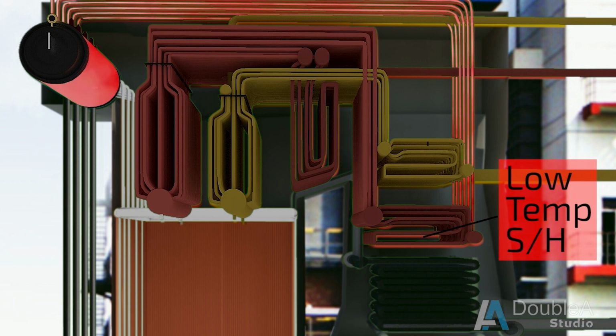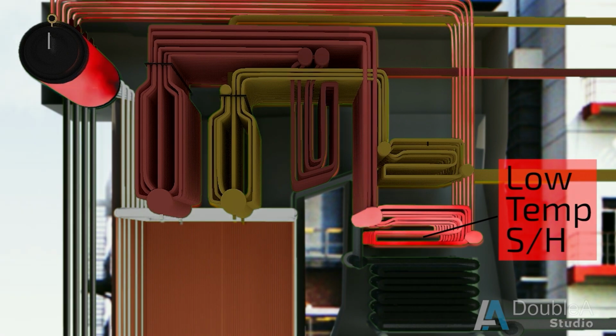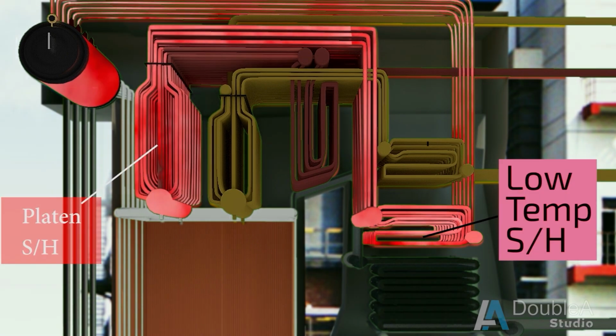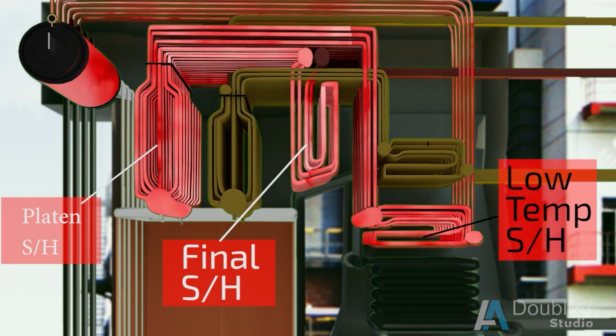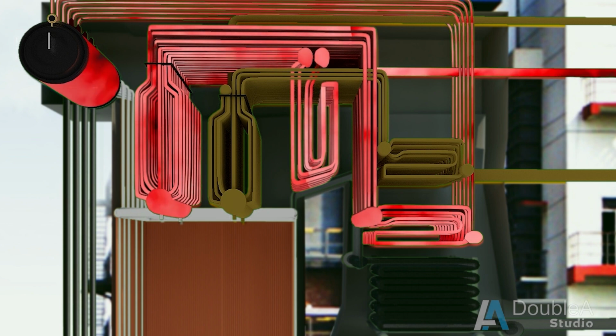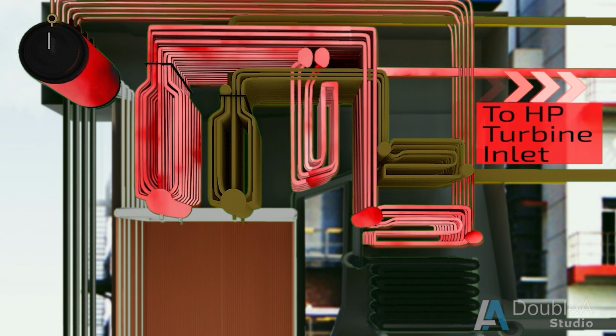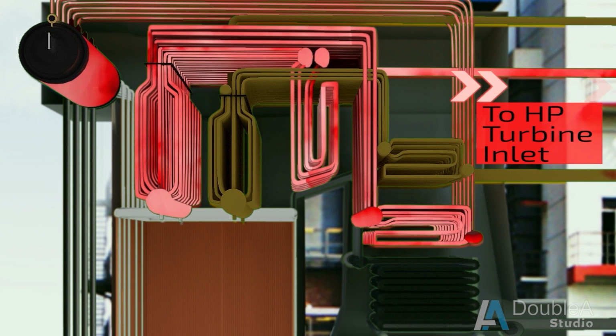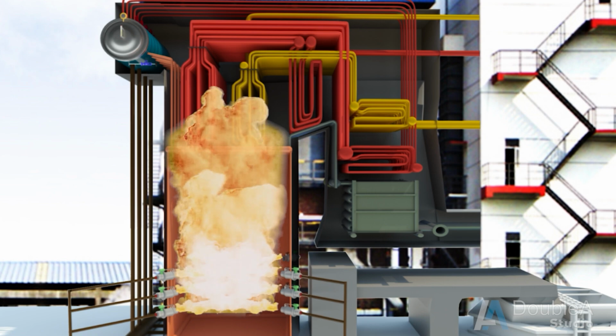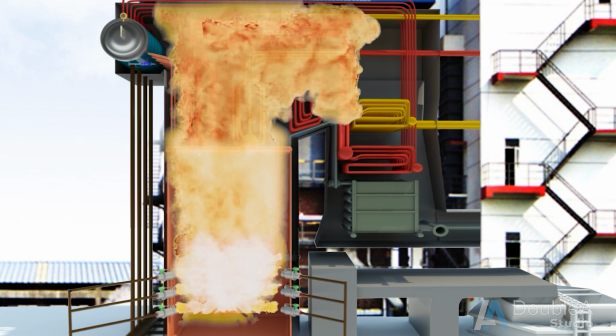After the boiler drum, saturated steam goes to superheaters for further heating. It goes first to the low temperature superheaters located in the second pass. From there, it goes to the platen superheater and then to the final superheater situated in the first pass of the boiler. After that, superheated steam is sent to the HP turbine. Thus, we see that superheaters increase enthalpy of steam, which increases work in turbines. It utilizes heat from flue gases and increases efficiency of the boiler.